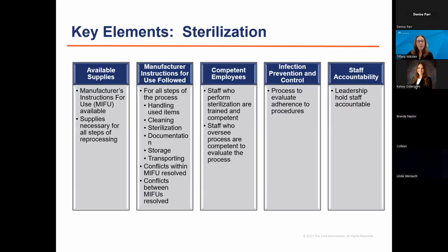So these are some of the key elements that our surveyors are looking for when they're reviewing sterilization processes. First, of course, is available supplies. And you're going to start to see this pattern here, right? The manufacturer's instructions for use are available. The supplies necessary for all steps of reprocessing are available. Manufacturer's instructions for use are followed for all steps of the process. So that is handling used items at the point of use, cleaning, sterilization, documentation, storage, transport. If there are conflicts identified within the manufacturer's instructions for use or between the manufacturer's instructions for use between, like, say, an instrument or device or a sterilization accessory, that those conflicts are resolved.